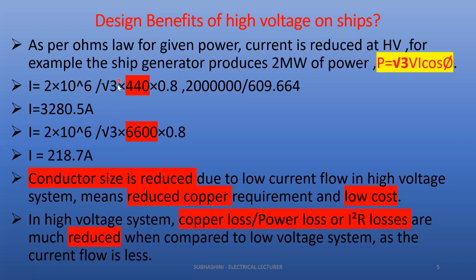Now I am stepping this 440 volt up to 6600 volt. This is high voltage, 6.6 kV. When 440 is stepped up to 6600 volt, the calculated current value is approximately 220 amperes.